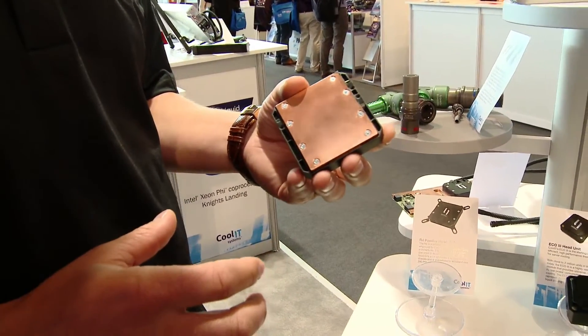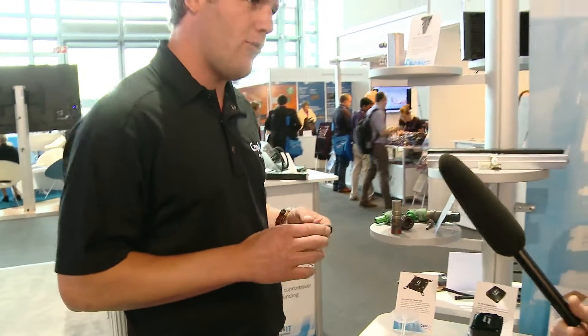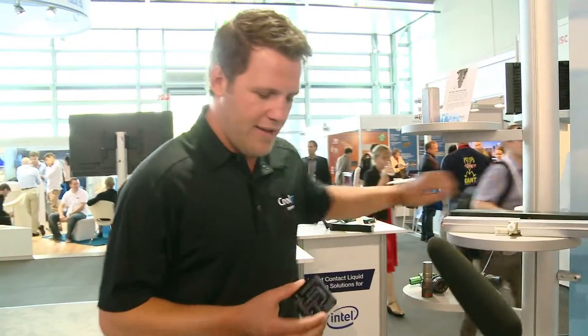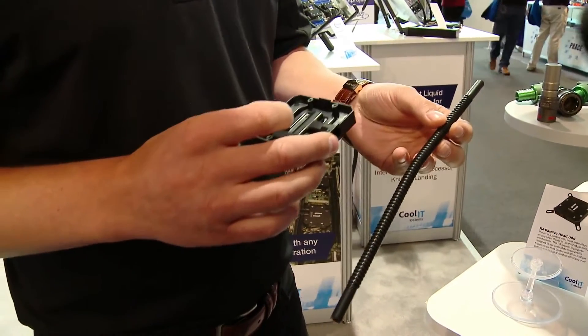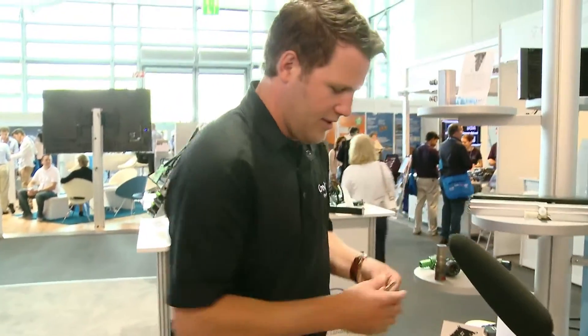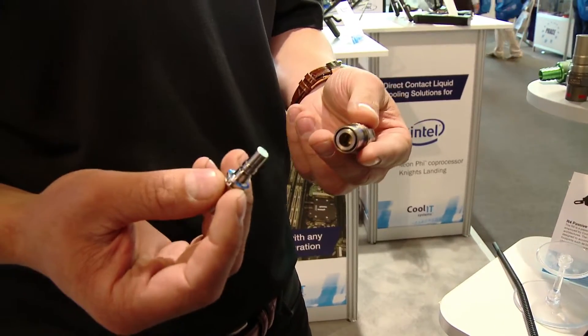The server module is comprised of a few key components. Number one is the cold plate, which is a big part of CoolIT's intellectual property. We generally sell passive cold plates with a centralized pumping system into the data center market. You have the cold plate, different sizes of tubing to negotiate through the server, and it terminates in a dry break quick disconnect. We use Stäubli metal quick disconnects — we think metal is very important for reliability and that it's a data center grade product.